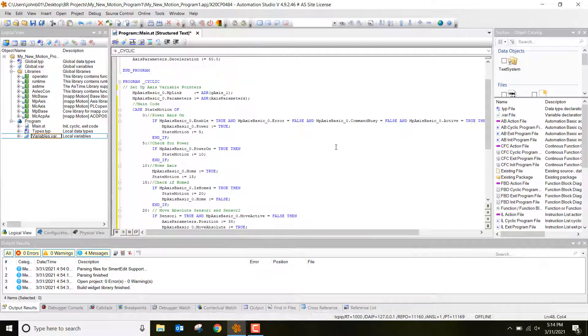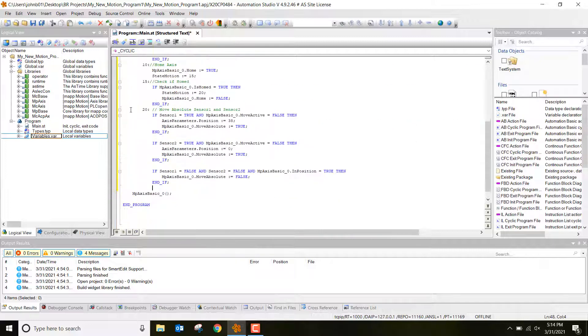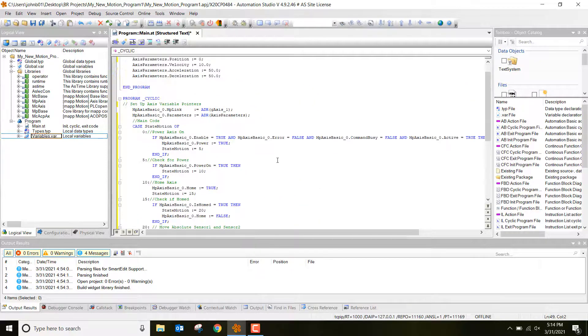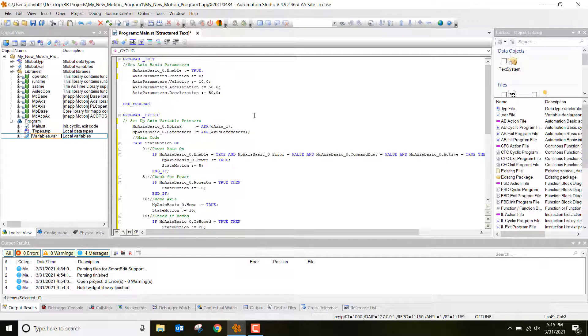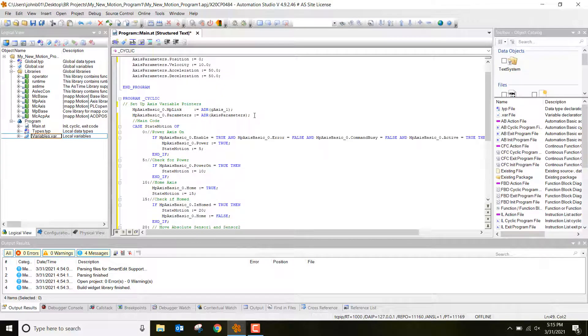One last thing: since we started the CASE statement, we have to end it — if you don't, you'll get errors. Go back one space and type END_CASE. And there you go — the program is written. This is how you do a basic case statement in structured text. Let's go ahead and build the project, transfer it down to our controller, and see the actuator move.